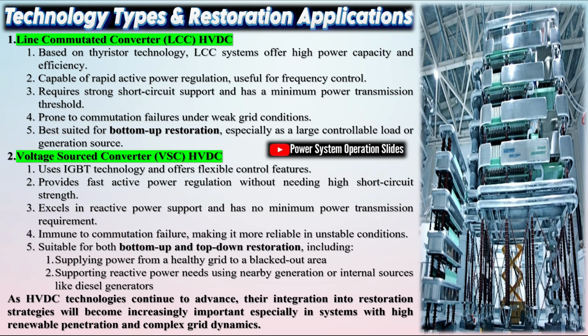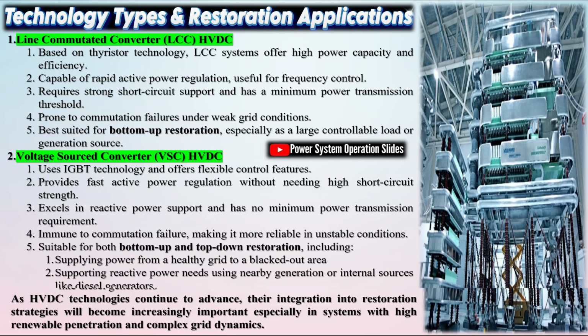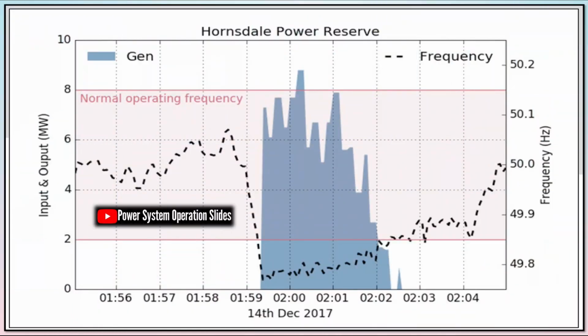Provides fast active power regulation without needing high short-circuit strength. Excels in reactive power support and has no minimum power transmission requirement. Immune to commutation failure, making it more reliable in unstable conditions. Suitable for both bottom-up and top-down restoration, including supplying power from a healthy grid to a blacked-out area, supporting reactive power needs using nearby generation or internal sources like diesel generators.